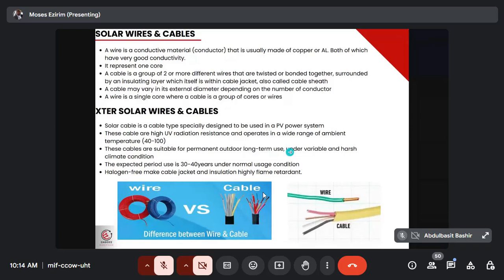Under climate conditions, the cable should be able to withstand it, and not all cables can. So if you're procuring cable for C&I installation, go specifically for solar wires. The expected period of use is 30 to 40 years under normal usage conditions. Also, halogen-free cable jacket and insulation make it highly flame resistant. That's the key point.